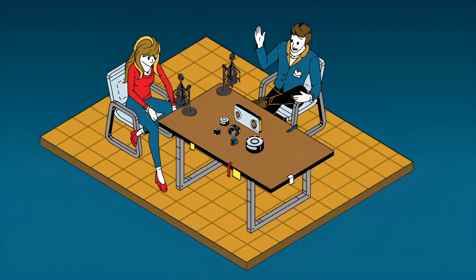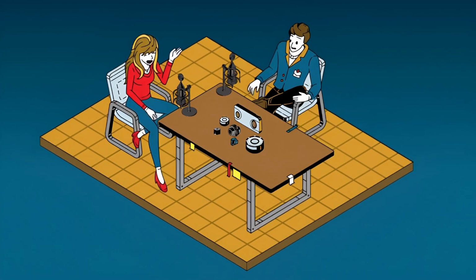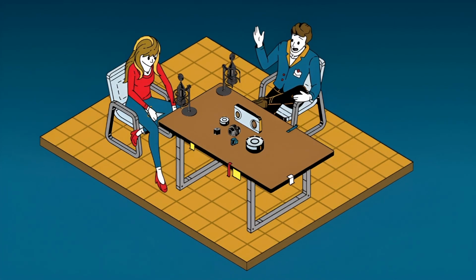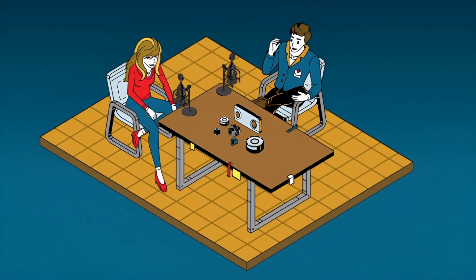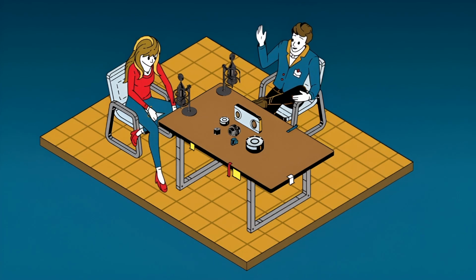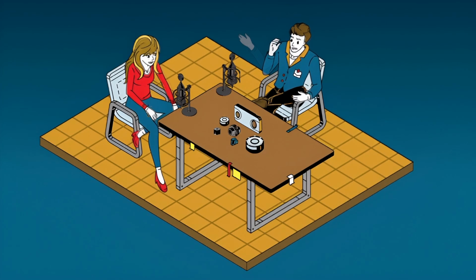And that's just the foundation. The tools they use for the calibration must be just as important as how often they do it. Well, absolutely. And what's fascinating here is the kind of hierarchy of measurement. A high-quality calibration uses reference materials like NMI certified gold and platinum standard reference load cells. NMI, so that's National Metrology Institute. Correct.